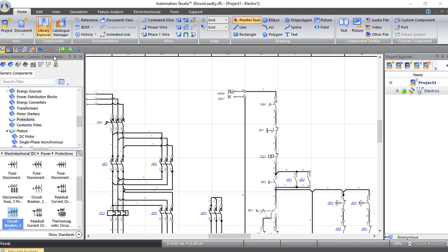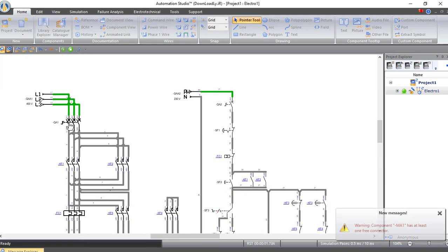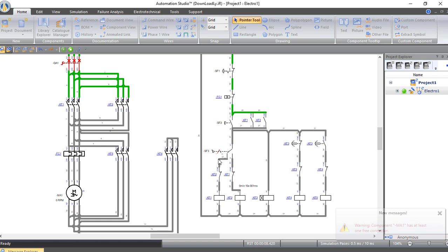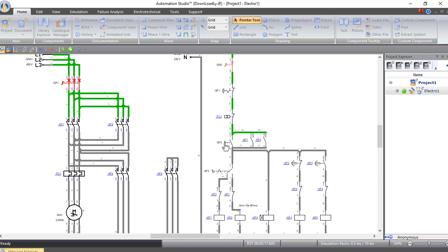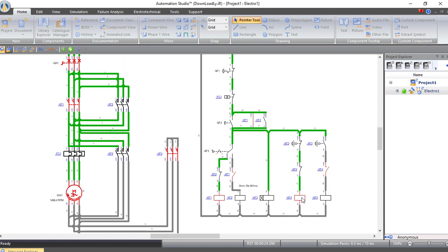Now let's simulate our circuit. We will close the main circuit breaker for the power circuit and the main circuit breaker for the control circuit. The selector is set to K1 so the motor will rotate in the forward direction. Let's press start — the main contactor and star contactor are now working. After 10 seconds it moves to work as delta, and we are now running on delta in the forward direction.